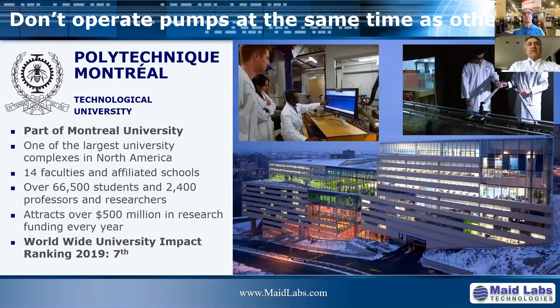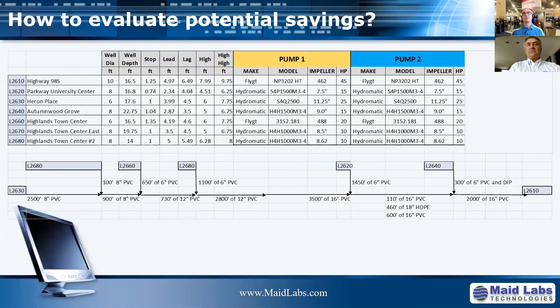Lead lag, these are the names given to the levels. The lead is the level at which you start your first pump, not necessarily pump number one, it's just the first one that would start. When you get to the lag level, that means it's the second pump that you would start, and that means you already have the first pump running, then that second pump starts.